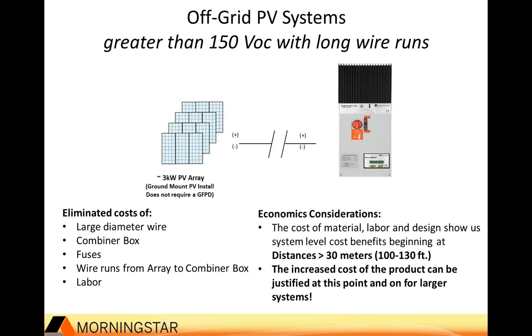For instance, talking to some customers in the northern part of Canada, they were often using homes or installing PV systems at homes that were in the woods, but they had a clearing available to put a ground mount PV array. But the distance and the wire gauge required to make that long of a run was not really practical. In this case, you can now do that because you can use smaller diameter wire. You eliminate the combiner box, fuses, the additional wire runs to the combiner box, and of course the labor associated with that. And we've done some calculations and found that the economic benefits really start to take place at about 30 meters and beyond.